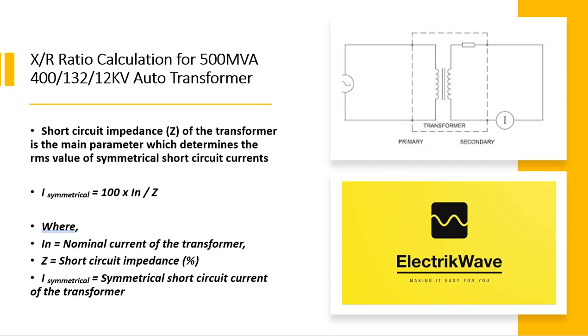Short circuit impedance Z of the transformer is the main parameter which determines the RMS value of symmetrical short circuit currents. In the mentioned formula, IN equals nominal current of the transformer, Z equals short circuit impedance, and I_symmetrical equals symmetrical short circuit current of the transformer.